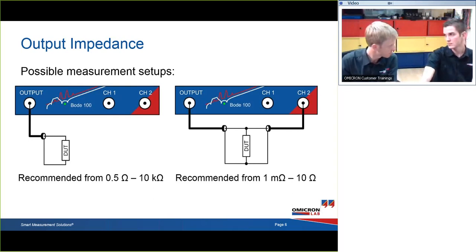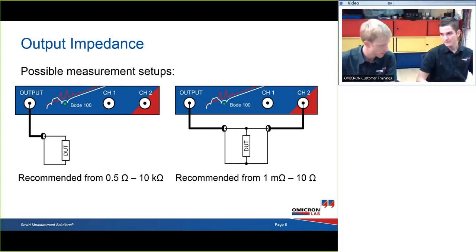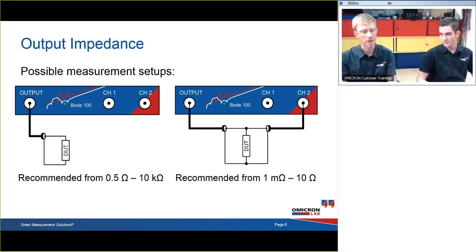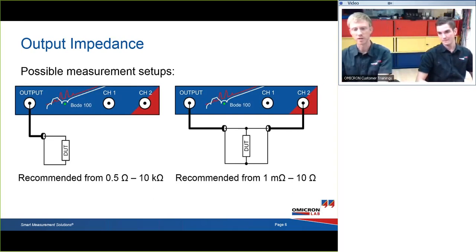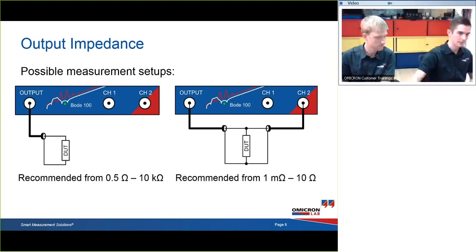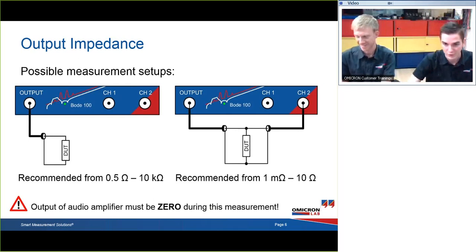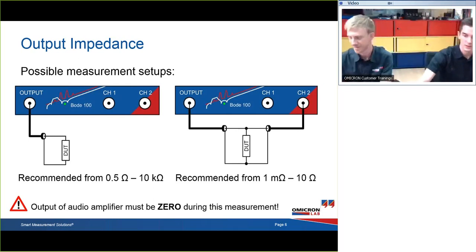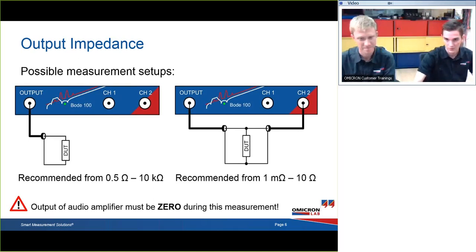In the shunt-through method, it's actually a gain measurement, so you need to convert the gain result to an impedance value using a simple formula. We have prepared an Excel sheet for that — please contact us if you're interested. Very importantly, when measuring output impedance, please ensure the input has no signal — short the input or leave it disconnected — so the Bode 100 can't be destroyed.